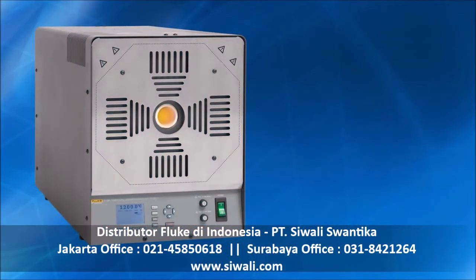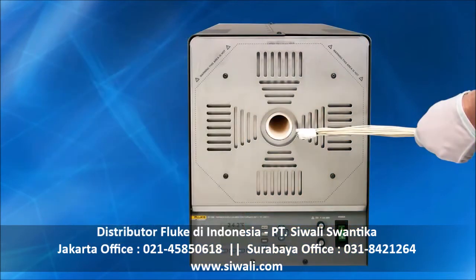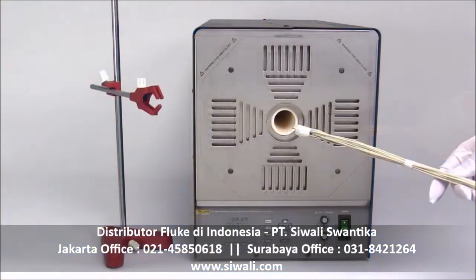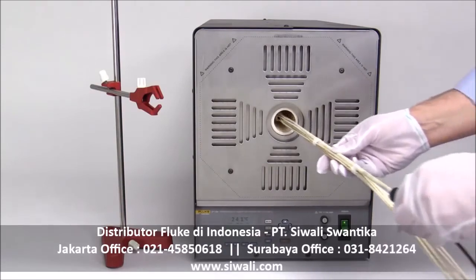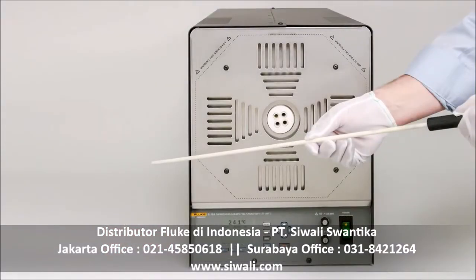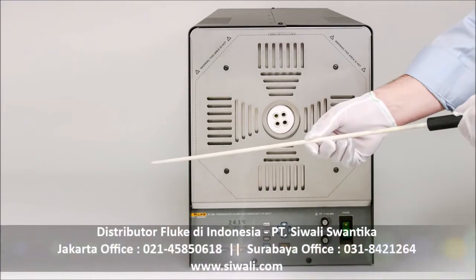The 9118A without an isothermal block is configured as a tube furnace for calibrating base metal thermocouples. These thermocouples are often wrapped in materials such as braided fiberglass or PTFE. During calibration, they're bundled around a reference thermometer held together with fiberglass cord and inserted into the 9118A. Metal or ceramic sheathed thermocouples are normally built with noble metal thermoelements and have higher calibration accuracy requirements.